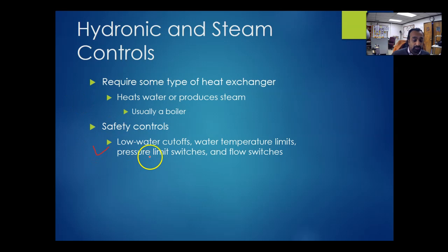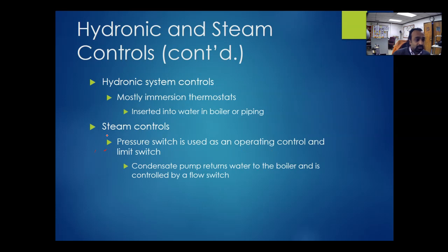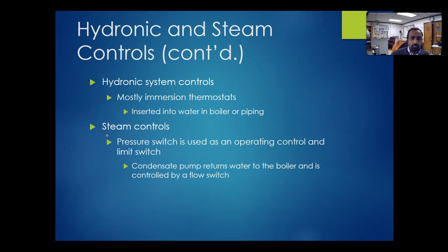For steam and hydronic controls, safety controls are important. The low water cutoff is the most critical part of a steam control, because the rate of fire going into the chamber is very high. Pressure switches are used to operate the system. These are the most common controls you'll see in chapter 14, pertaining to heating systems. We'll touch base on each of these during the energy systems lab, where you'll get exposed to those sensors and controls for the flame, fire rate, airflow, oil, water, and steam. I'll add this video to week three — let me know if you have any questions.